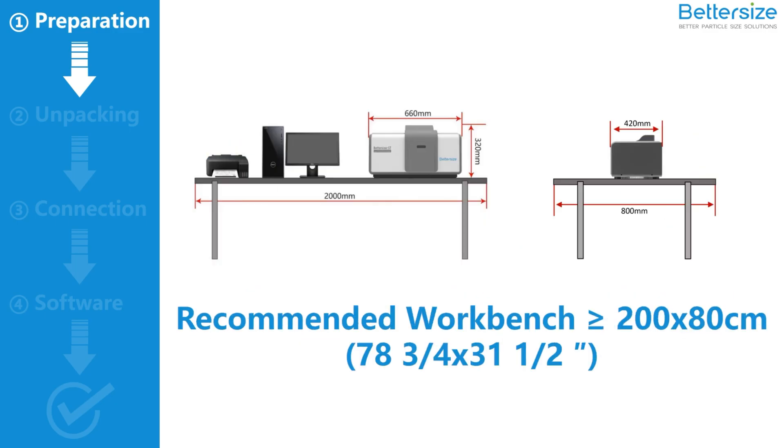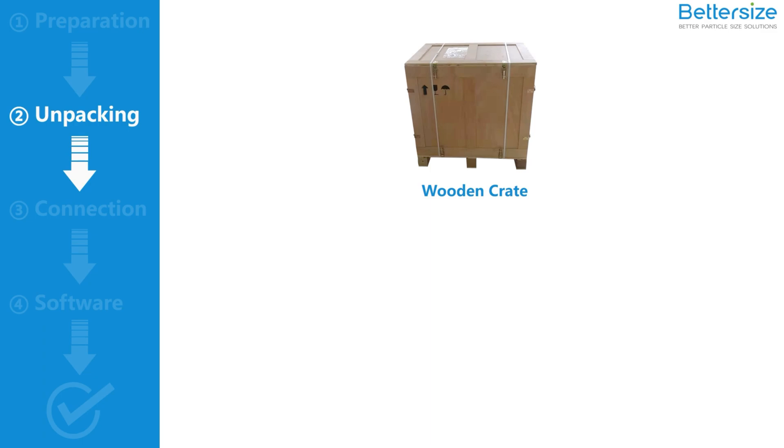The workbench should be rigid, and its length and width should not be less than 200 by 80 centimeters. After the preparation, unpack the wooden crate from the side. You will find a carton and a black service kit. The Bettersizer ST is in the carton — take it out carefully. The service kit contains various accessories for installation and maintenance.